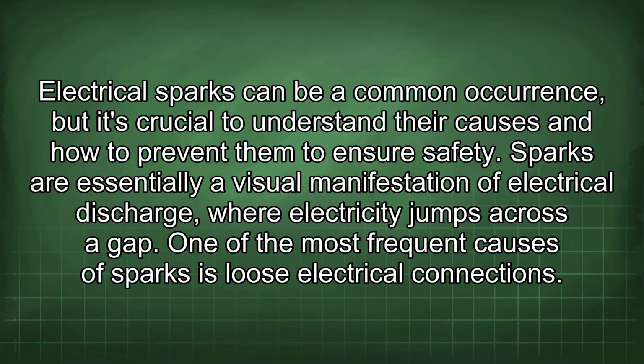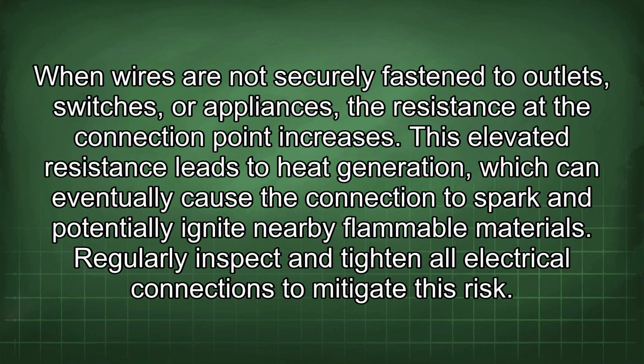Electrical sparks can be a common occurrence, but it's crucial to understand their causes and how to prevent them to ensure safety. Sparks are essentially a visual manifestation of electrical discharge, where electricity jumps across a gap. One of the most frequent causes of sparks is loose electrical connections. When wires are not securely fastened to outlets, switches, or appliances, the resistance at the connection point increases. This elevated resistance leads to heat generation, which can eventually cause the connection to spark and potentially ignite nearby flammable materials. Regularly inspect and tighten all electrical connections to mitigate this risk.